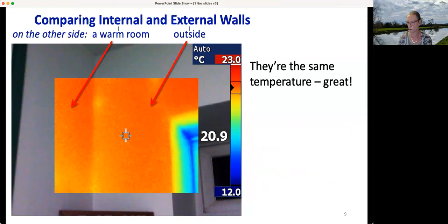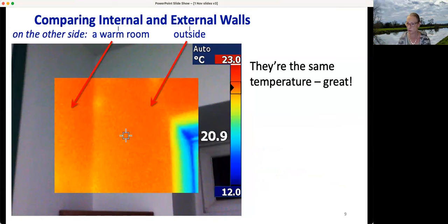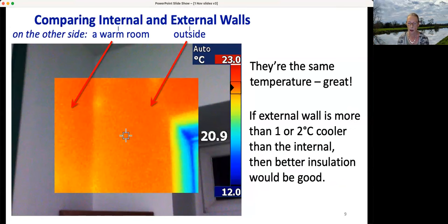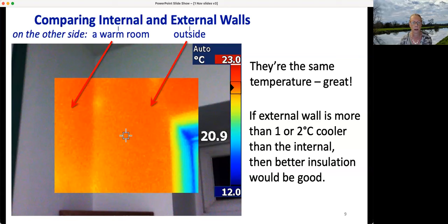If you look at an internal wall with a warm room on the other side, there shouldn't be any heat transfer, because it's warm on both sides. But if you've got an outside wall, you're going to get heat lost to the outside, so the inside surface of the outside wall will be cooler. If it's not much cooler, that's brilliant — it means well insulated walls. But if it's more than a degree or two cooler, it could really use some insulation.